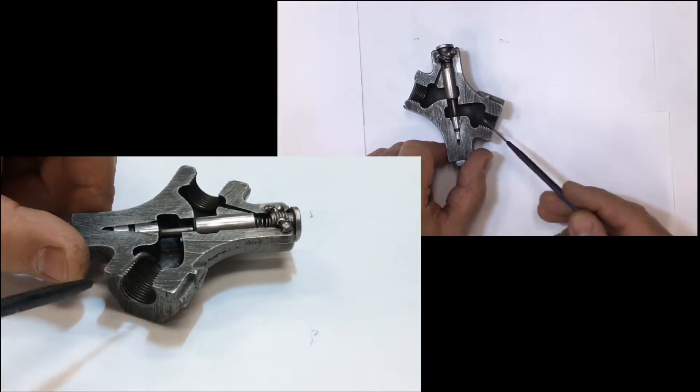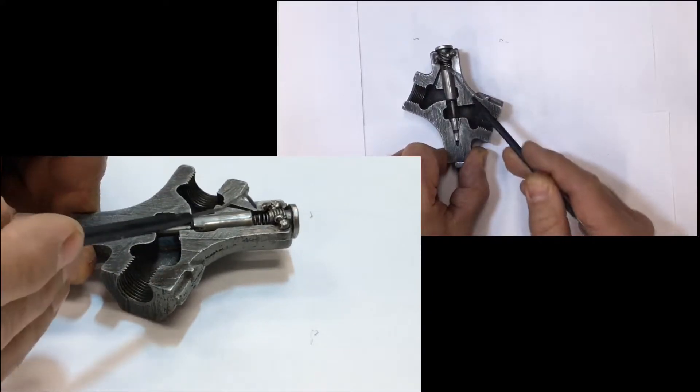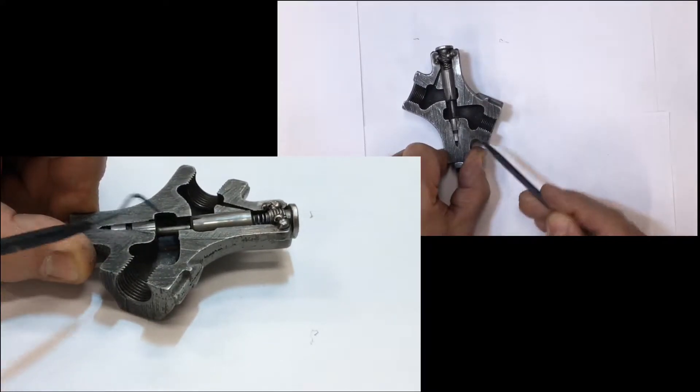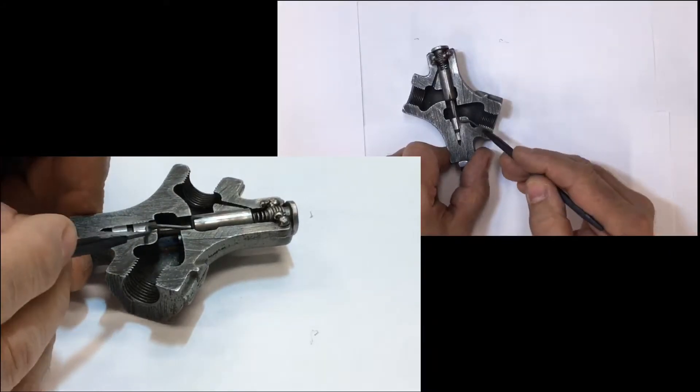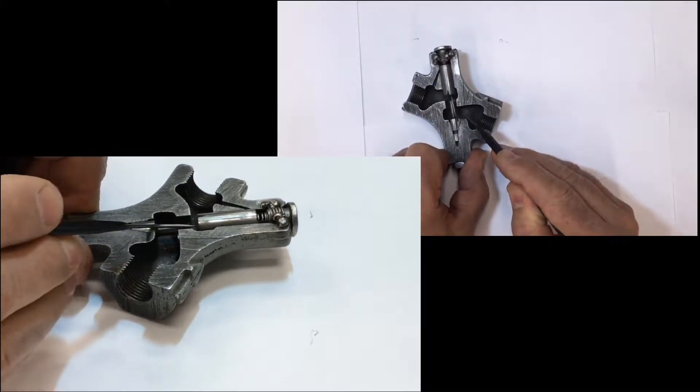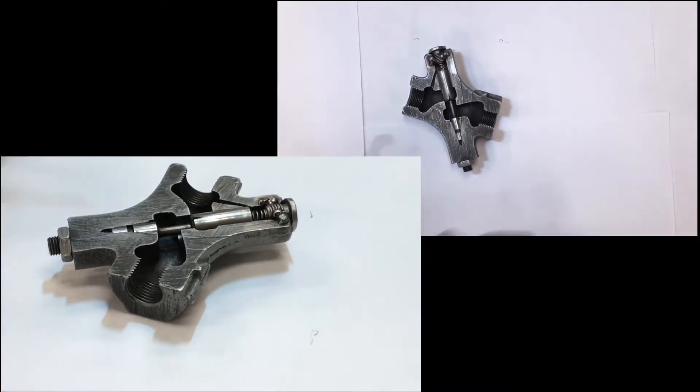What I mean by that is oil would come in, lift this light check ball with this light spring in there, and flow through the other end. Really all it has to overcome is this light three-pound spring behind this check ball.